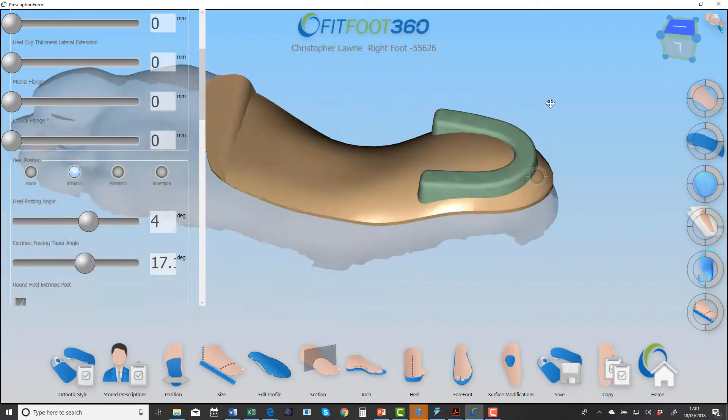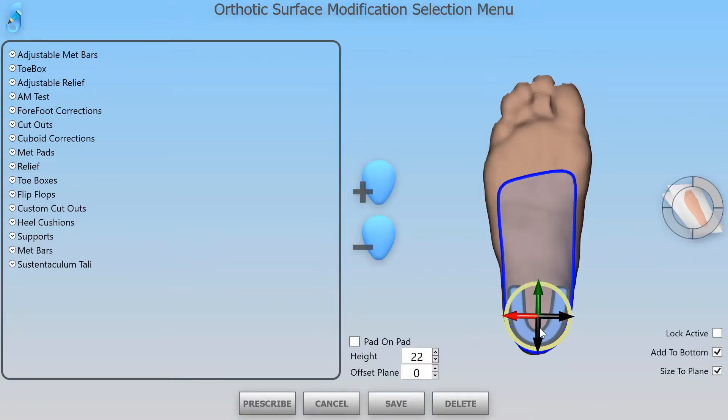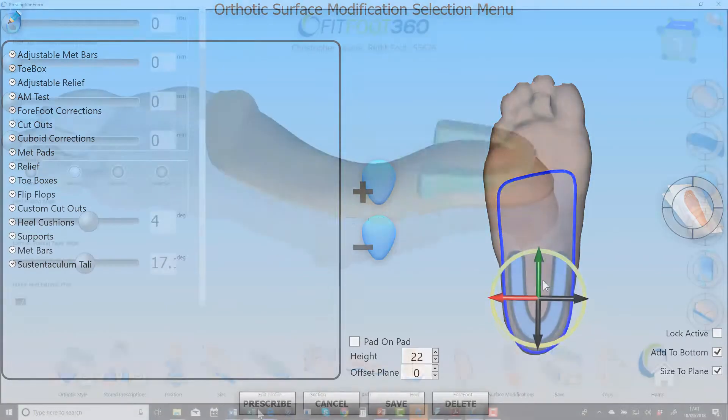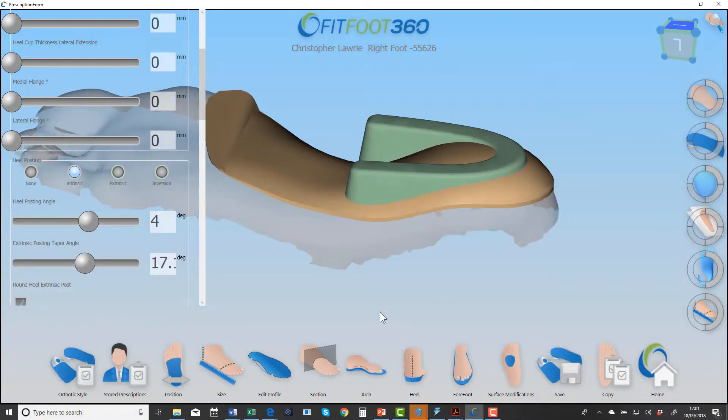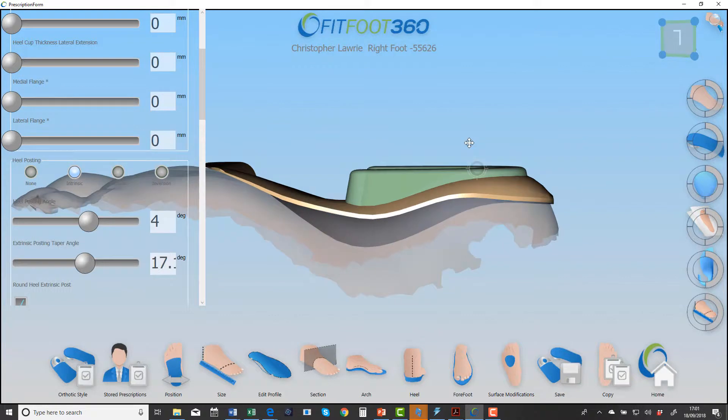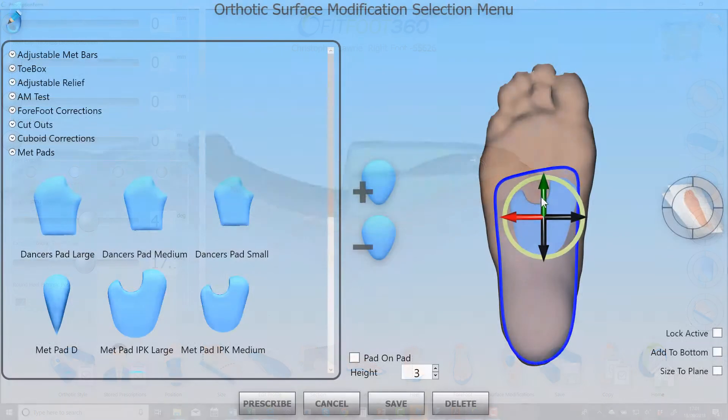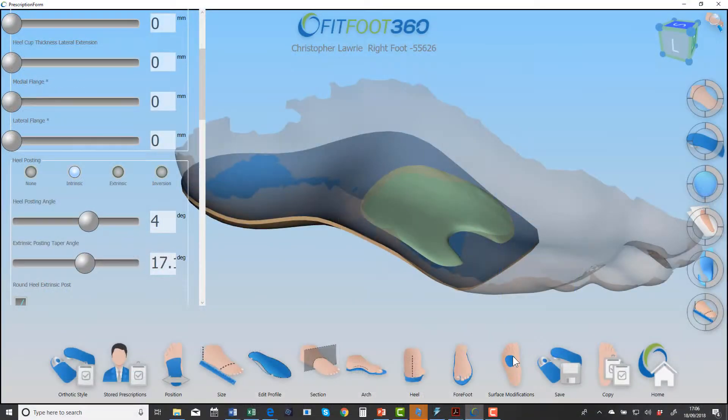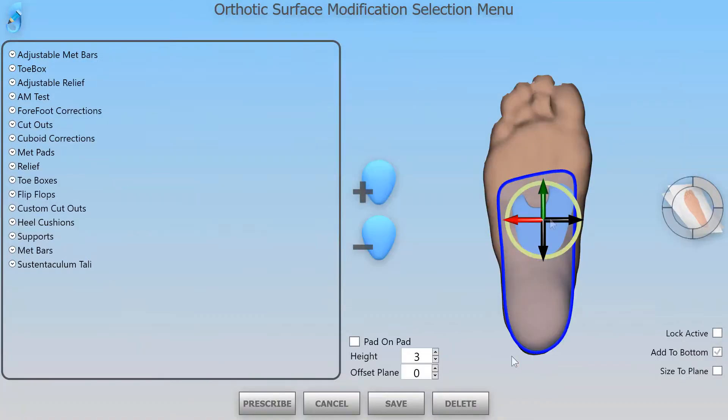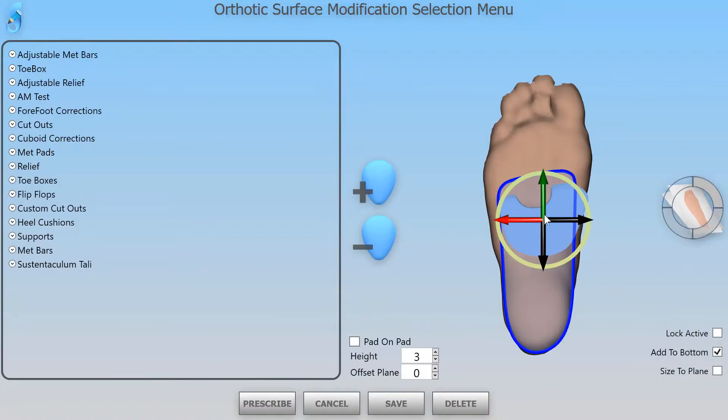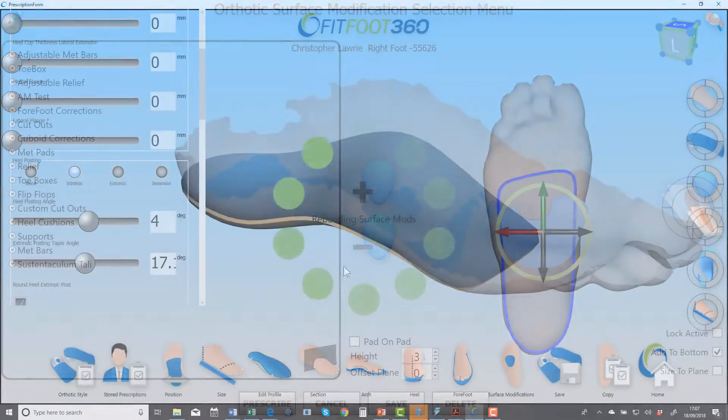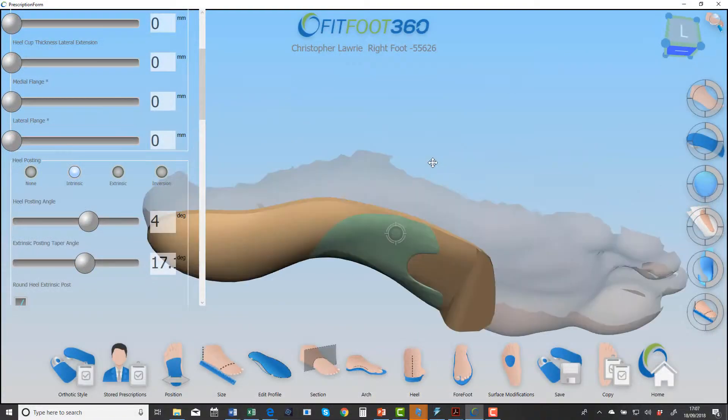The most important thing is you don't make decisions that are going to make the device weaker. So you could use a pad that you would use clinically, instead of using it on the top surface, use it on the bottom as support.